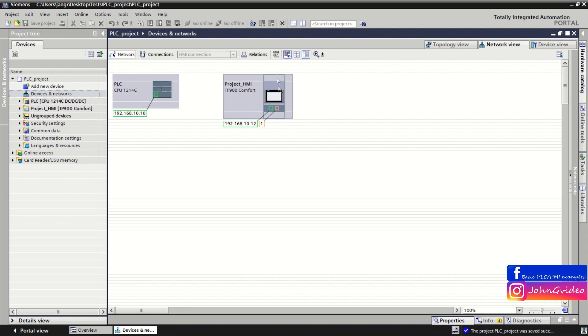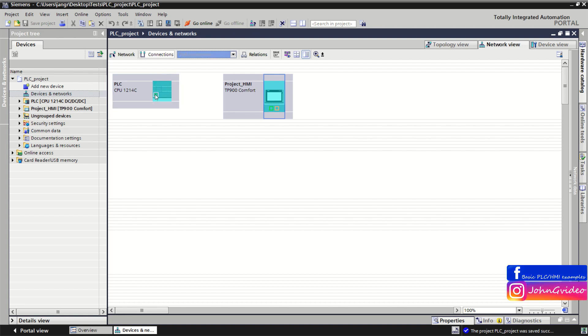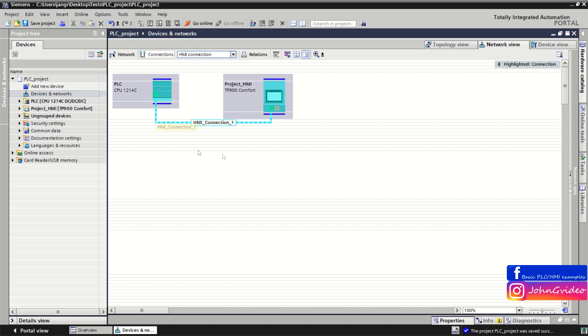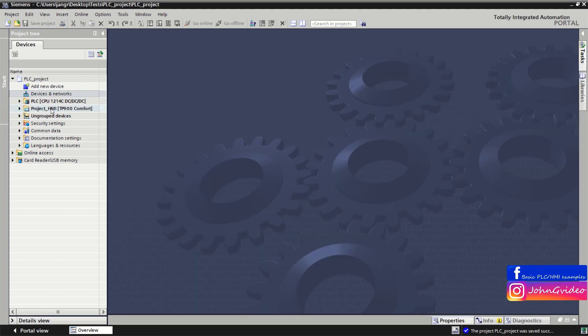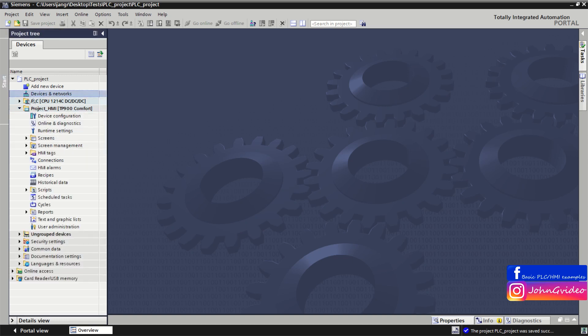Go back to the Device and Networks window. The next step is to create the connection between the HMI and the PLC. Click on the Connections button, choose HMI Connection, and then just drag and drop from the PLC port to the HMI port. As you can see, we have now created the connection between the PLC and HMI. Save this.